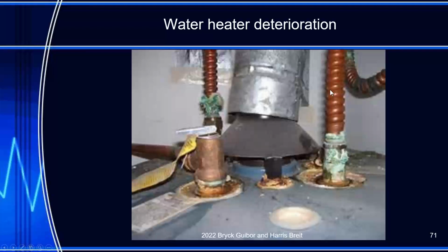for, what's it called? When the ground shakes, what's that called? Earthquake. Earthquakes, thank you. And it moves back and forth. So it used to be you had to have a hard pipe connection at the top and a hard pipe connection at the bottom. Well, that was the first thing to break. The water heater would snap off and gas would fly around and everything starts exploding.